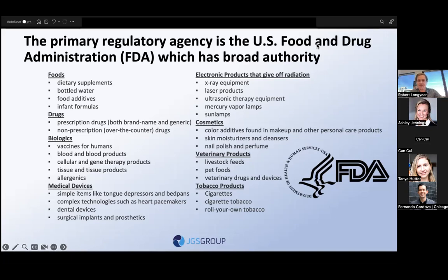Basically, your device, if it has an indication of use, will certainly fall under the FDA. There are some easier pathways where we could sometimes look at something and say we don't need to necessarily say that it is used as a diagnostic aid or a diagnostic device for this particular disease. We can kind of cut the actual definition of what the device is off at a different point. Sometimes what we see is there's actually an output from your device or technology that is fundamentally not necessarily tied to a particular condition, and that can sometimes lead to an easier FDA approval or registration process.